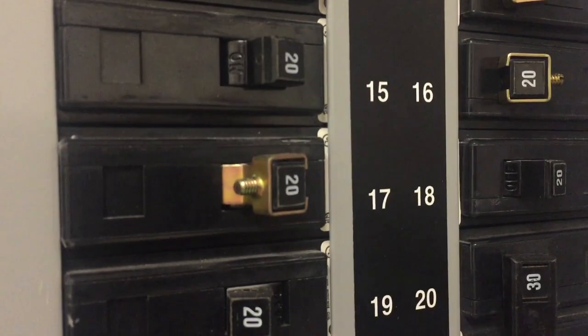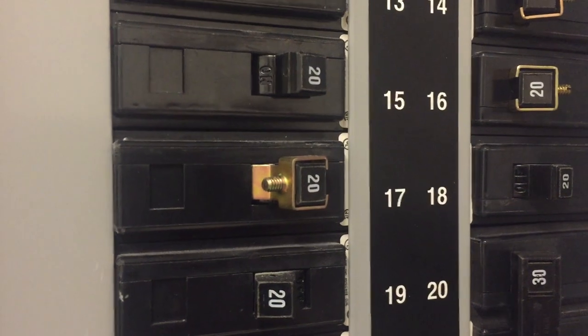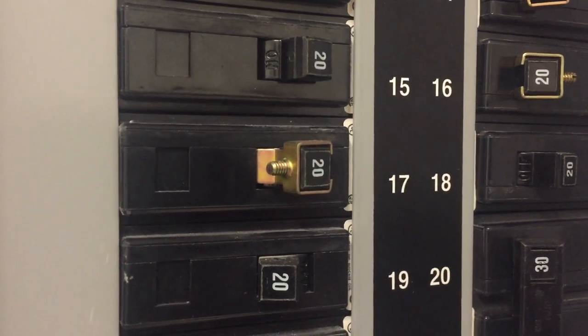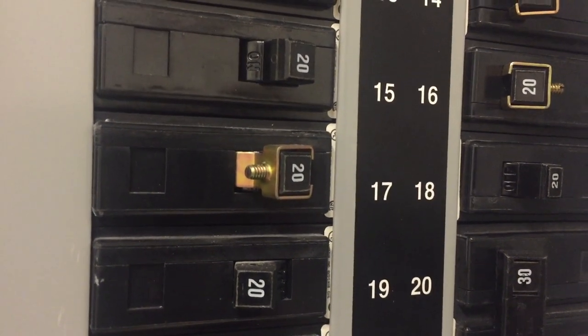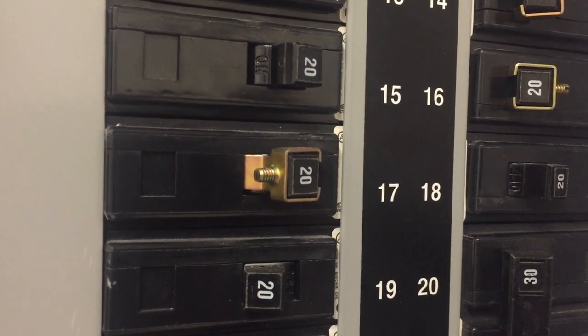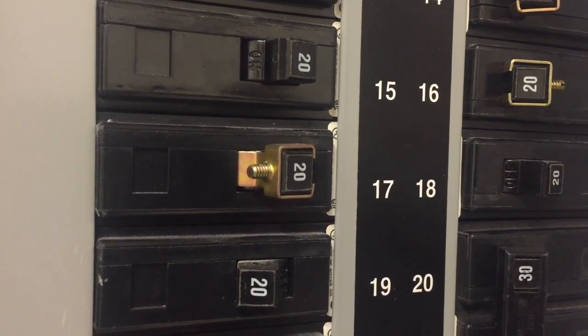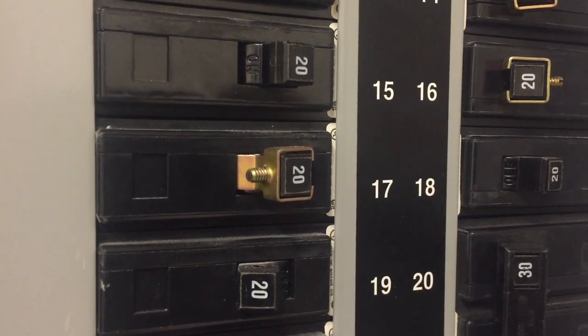And if you need to use a screwdriver to remove these breaker locks, that does not meet the definition of readily accessible. Now there are other types of circuit breaker locks that use thumb screws or something other than a screwdriver, for example. Those would be okay, but this style here is not code compliant.